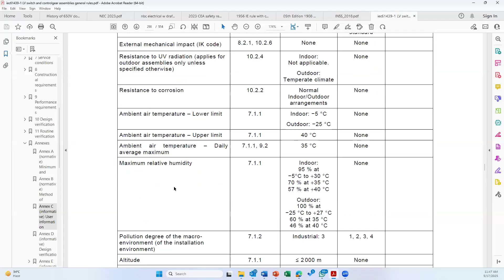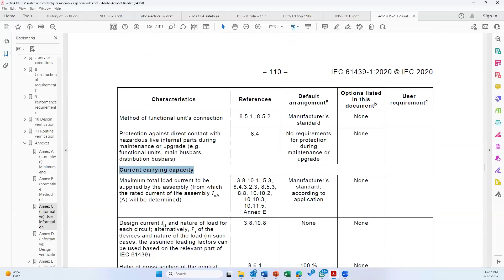Then I'm scrolling down. There are about 30 plus requirements. Installation method, what kind of installation method? Is it floor mounting, wall mounting, and so on. Storage and handling, operating arrangements, maintenance and upgrade capabilities, current carrying capacities, and so on. So basically, to select a switchgear or control gear, the user or the designer, the electrical consultant, is supposed to fill up this entire information. If some information is not applicable, they can put NA, not applicable, and give it to the user. And this becomes the basic document for the panel builder to understand what and where this item is going to be used and how, and what kind of subjects he has to take care of.